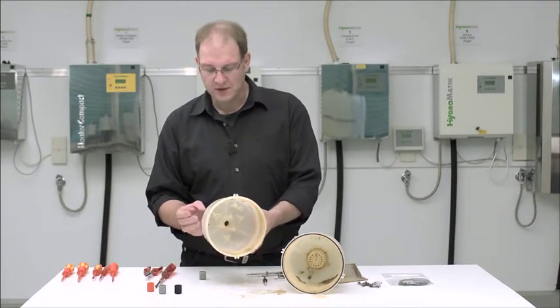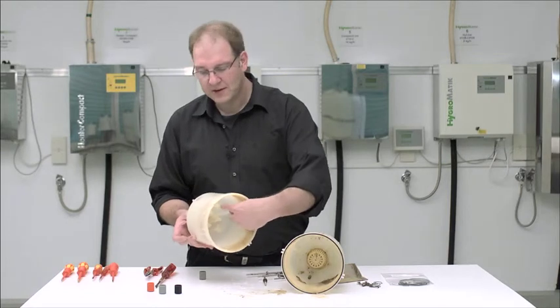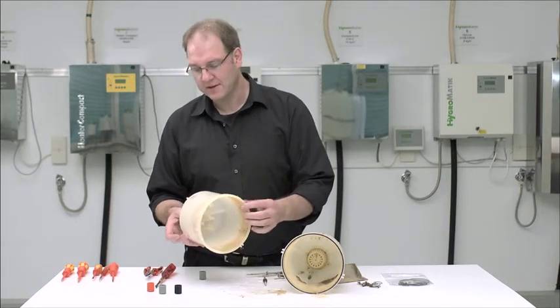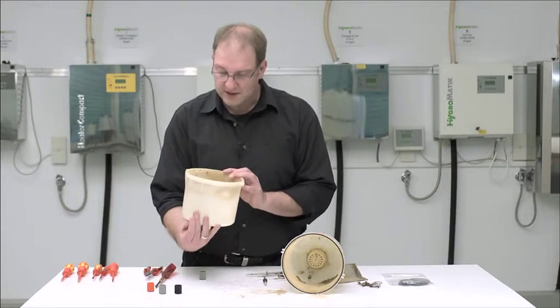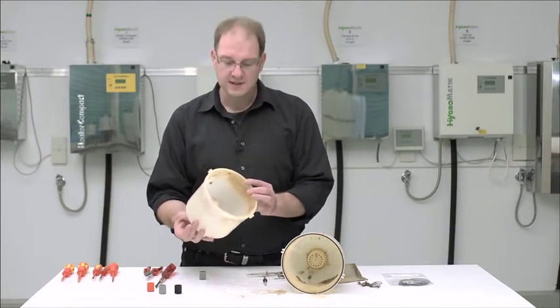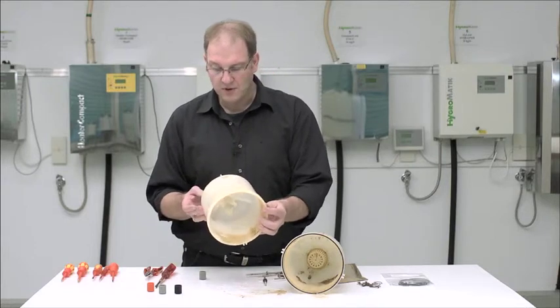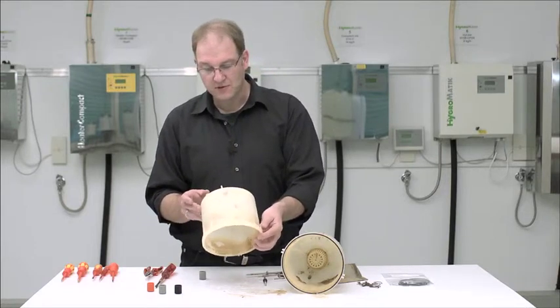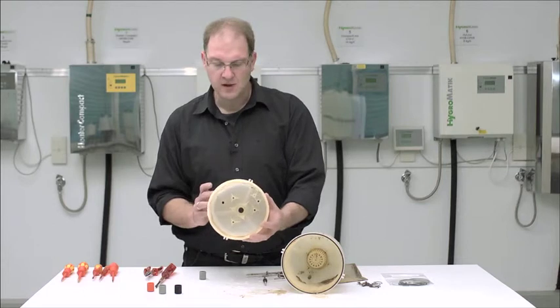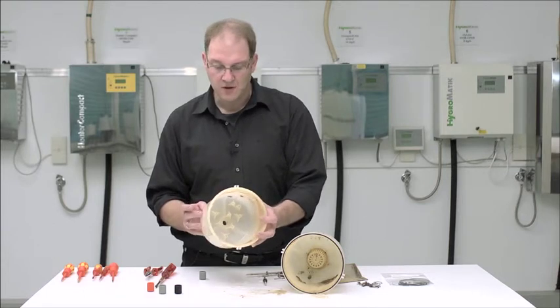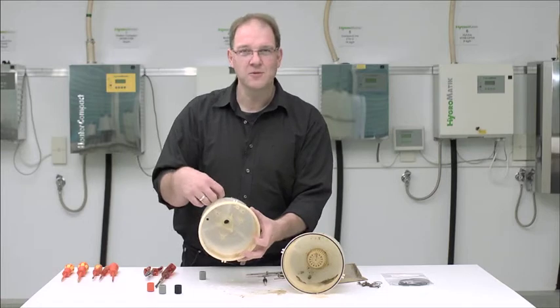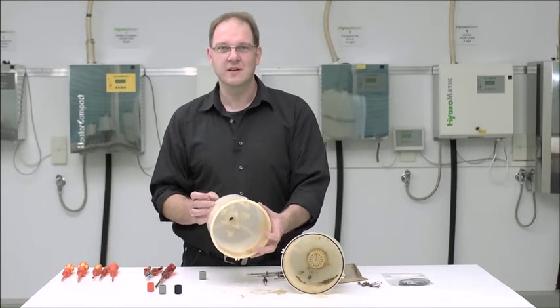I would really like to mention a certain point, and that is to please also perform the cleaning at the top of and inside the cylinder, because there too, minerals as well as salts, can deposit, and then sometimes up top here certain connections with the sensor electrode could be generated, which could at some point possibly produce interfering signals. Also, here as well, in the inside, around the base of the electrodes, clean very well, that would be important.